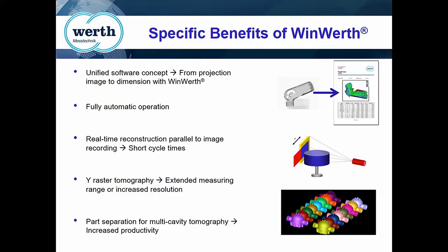WinWerth is a unified software concept. You do everything in that one software, from the projections all the way through to the dimensional measurements. We can do real-time reconstruction of your part, and you're also able to scan multiple parts at one time if they all fit in the detector and they are physically separated from each other within the fixture.